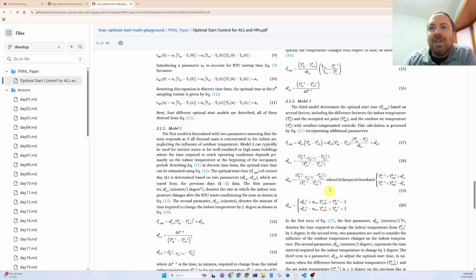It's just 14 days of data that'll get saved in terms of performance history. So it would just be the temperature that it took to this delta temperature here. So that's the set point, the occupied zone set point, and then the temperature that we ran the optimal start algorithm. So that difference, if the zone, like it's cold in the wintertime, so if the zone sinks below set point 8 degrees and we have to warm it up, that's this temperature difference.